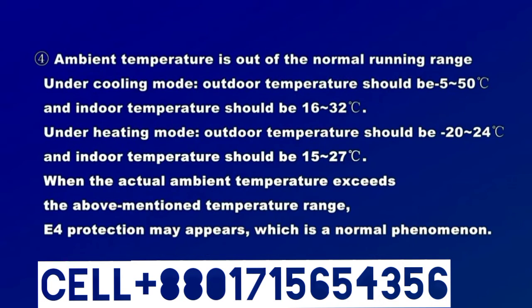4. Ambient temperature is out of the normal running range. Under cooling mode, outdoor temperature should be -5 to 50 Celsius degree, and indoor temperature should be 16 to 32 Celsius degree. Under heating mode, outdoor temperature should be -20 to 24 Celsius degree, and indoor temperature should be 15 to 27 Celsius degree. When the actual ambient temperature exceeds the above-mentioned temperature range, E4 protection may appear, which is a normal phenomenon.